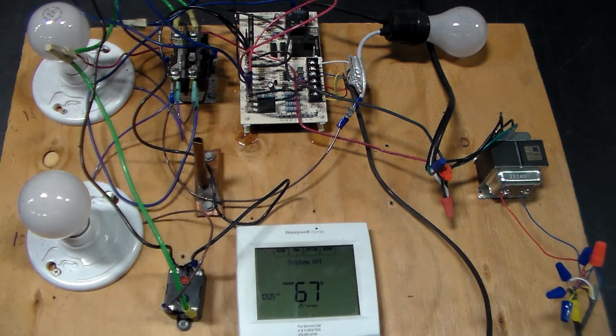So we mentioned earlier that W wire on the thermostat wiring. On this one it's labeled W1, sometimes it's labeled W2, and with Rheem and Ruud it's actually labeled D. Why would it be labeled D? Because of defrost. We talked about defrost earlier. When the heat pump goes into defrost, it's going to shift into cooling. It's going to turn off that outdoor fan to get the head pressure up, because we're basically running AC now in the wintertime. And as we should all know by now, ACs don't like when it's cold outside. So we cut that outdoor fan, it gets the head pressure up. It also puts more heat onto that outdoor coil to help it defrost faster.